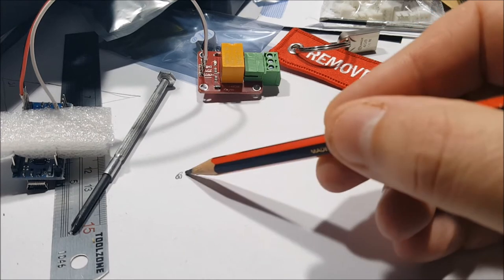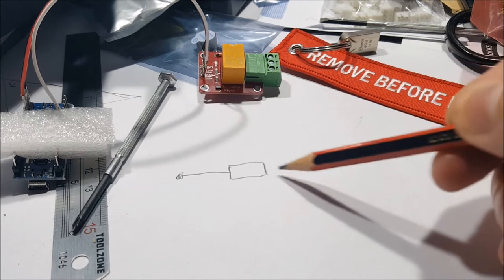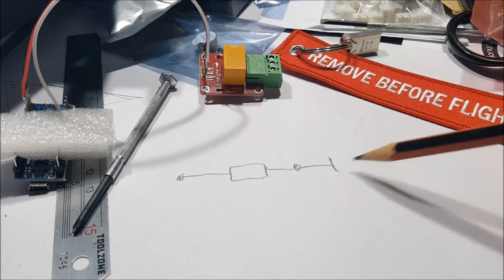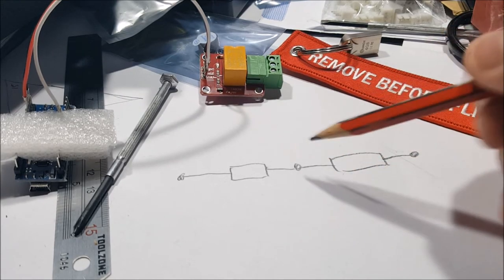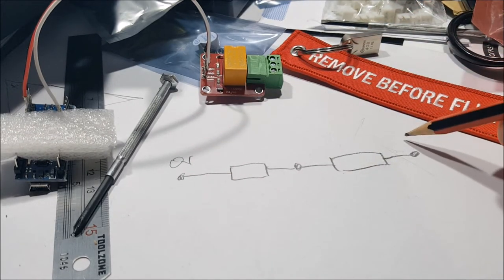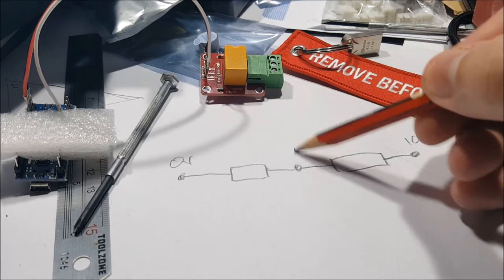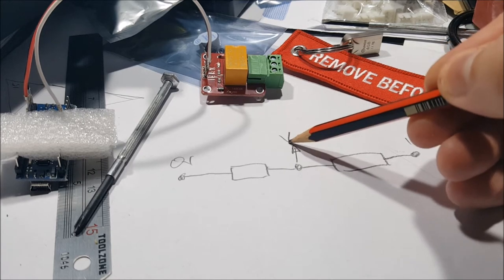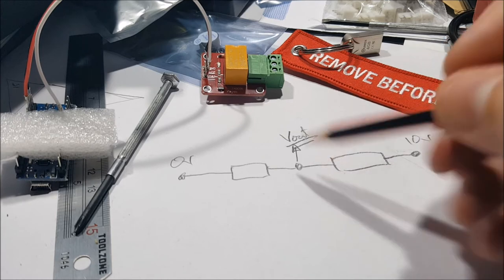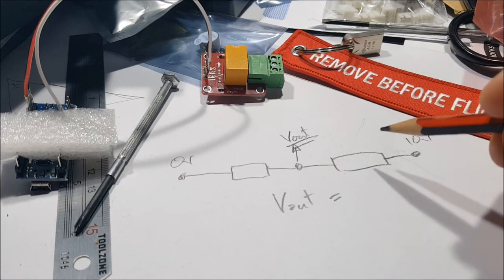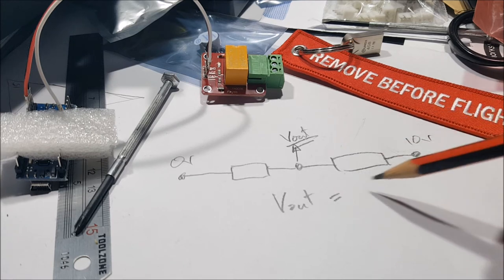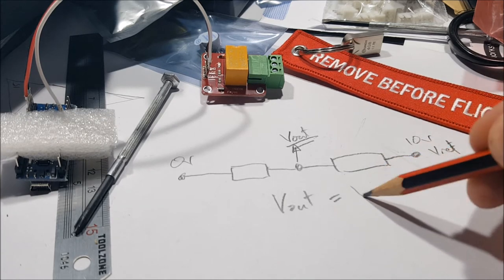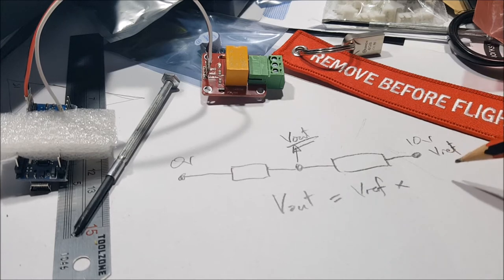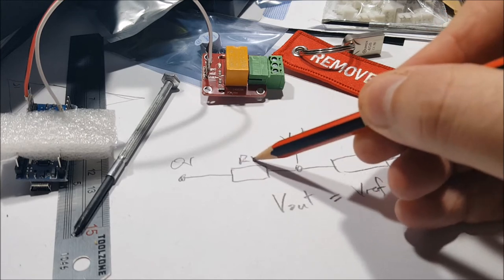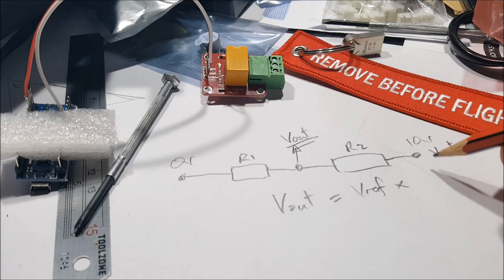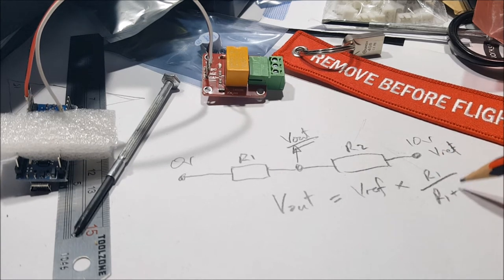Basically what the temperature controller does is it uses what's called a Wheatstone bridge, which is basically you measure a voltage between two resistors, and because we've got thermistors, one of those resistors will change in resistance. It works basically with this maths, so I'll take you quickly through that. If you've got a voltage, the center voltage between the two resistors, the output voltage is a function of the two resistors. And the function is that basically it's equivalent to the ratio of the first resistor divided by the total resistance. So the reference voltage times, let's label these up. Call that R1 and call that R2. So it's Vref times R1 over the sum of R1 and R2.